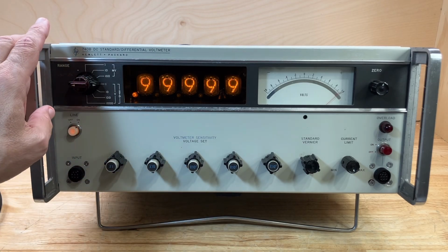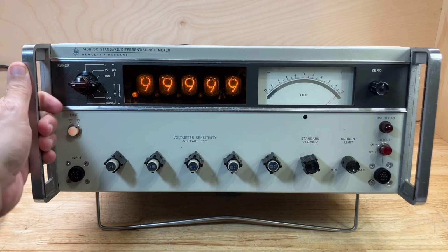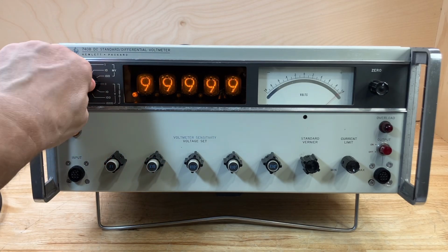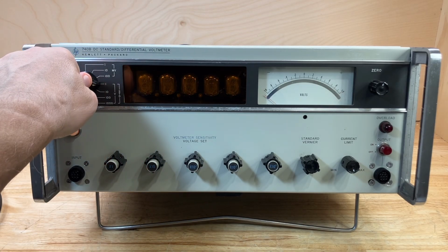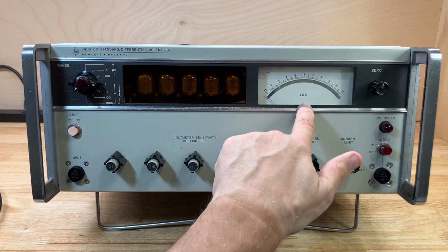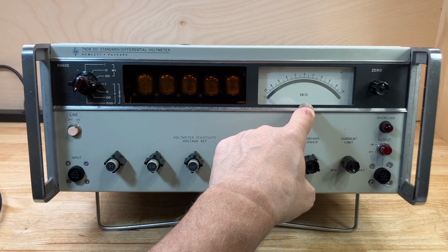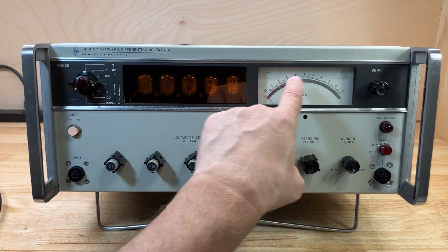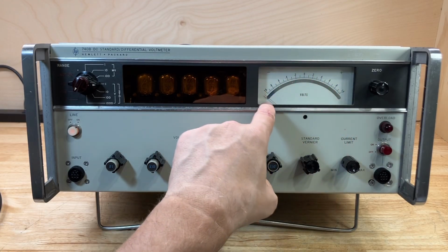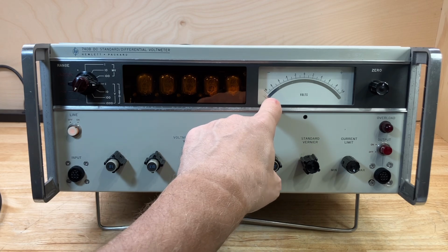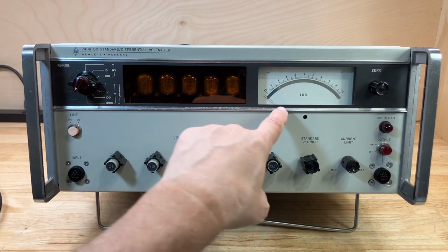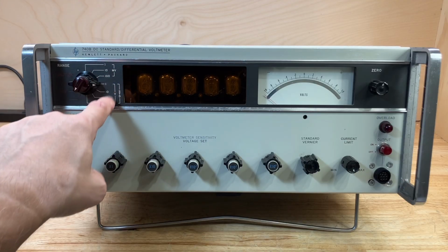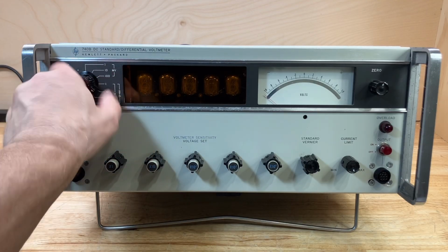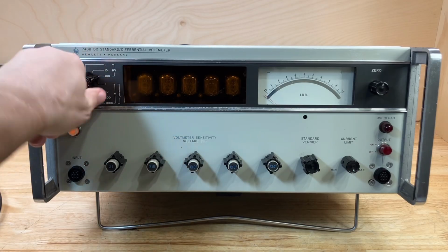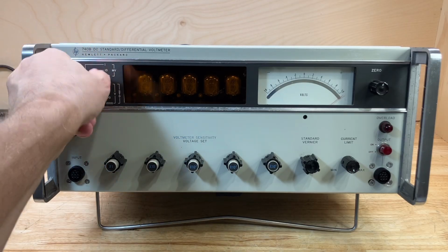In addition to being a DC standard for calibrating voltmeters, it has other functions. It can be used as an ordinary zero-center DC analog voltmeter, so it can read plus and minus voltages without reconfiguring the input terminals. That voltmeter has ranges from 1 millivolt up to 1,000 volts, which can be selected with the range selector switch here. So you can measure as low as 1 millivolt and as high as 1,000 volts using the DC voltmeter function of this instrument.